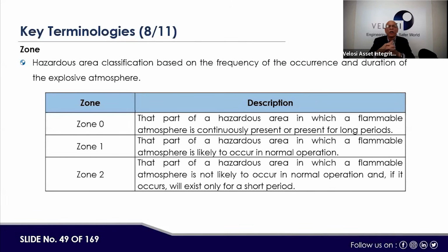Then zone 1 is above the tank surface, where there could be a potential presence of the hydrocarbon for a long period, but not continuously. That is the part of a hazardous area in which a flammable atmosphere is likely to occur in normal operation. Then zone 2 is the part of a hazardous area in which a flammable atmosphere is not likely to occur in normal operation, and if it does occur, it will exist only for a short period.